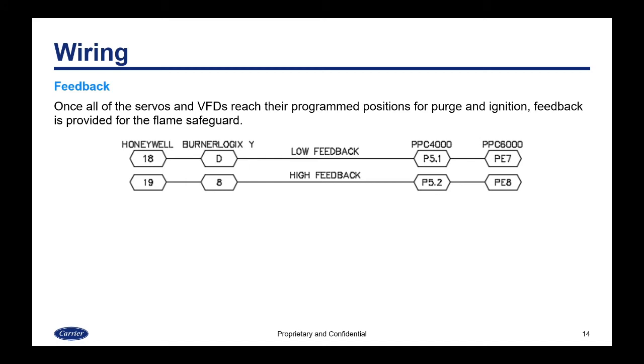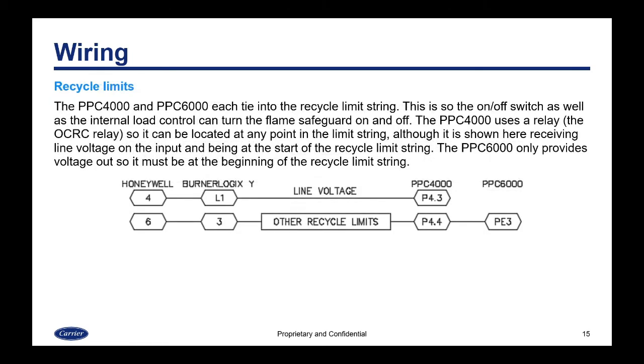Once all of the servos and VFDs reach their program positions for purge and ignition, feedback is provided for the flame safeguard. The PPC4000 and 6000 each have terminals for this that go back to the flame safeguard's low feedback and high feedback terminals, and those terminals may have different names. The PPC4000 and 6000 each tie into the recycle limit strings. This is so the on-off switch on the touchscreen or on the keypad, as well as the internal load control, can turn the flame safeguard on and off as needed.